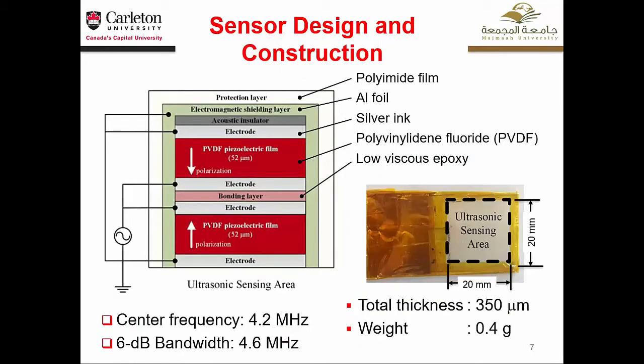This shows the sensor design and construction. The main material, the red one here, is a piezoelectric polymer material. We chose polyvinylidene fluoride, PVDF, which is a kind of standard polymeric piezoelectric material. We glue two films, each with a thickness of 52 microns, using low viscosity epoxy.